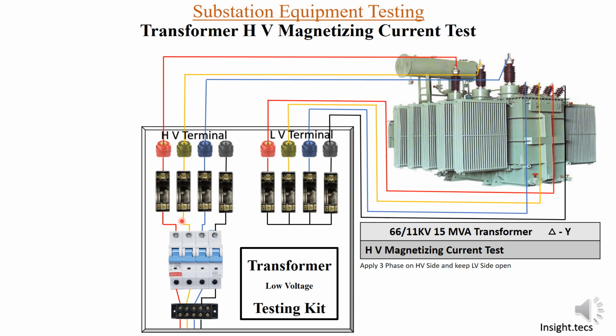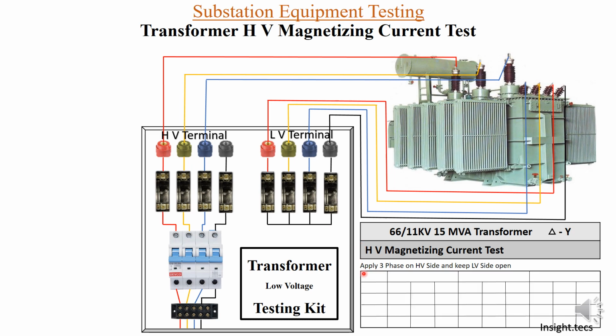Let us connect now, and before that let us see the format in which you will get the results for the HV magnetizing current test. We have to check various steps. We have various step numbers, then the voltage measured on the HV side between RY, YB and BR phases, and we will see the HV current measured in milliamperes.